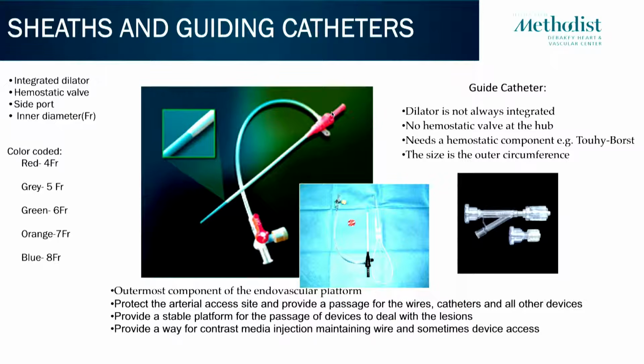And one of the mistakes that you see happening is if you don't have a big enough dermatotomy, then what happens is, as you advance this dilator, the dilator pushes back and you see the dilator at the hub separate from the sheath. Well, that means that you don't have a good transition. You don't have that nice tapered transition. So it's one of the things you need to watch: make sure that this dilator stays engaged and locked into that sheath, because it can certainly push back.